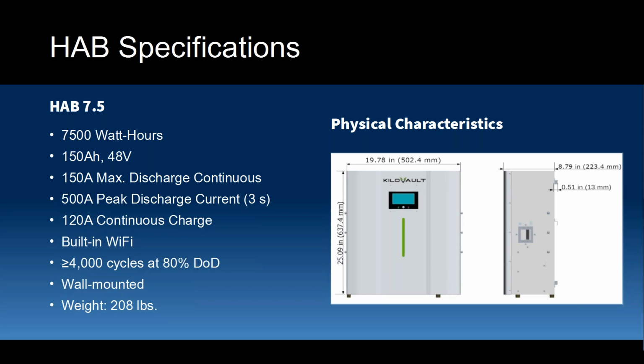At 80% depth of discharge, you'll get approximately or at least 4,000 cycles. We rate it like that because it really depends on how you are cycling the battery. If you're always charging and discharging at the max allowable current, you'll probably get 4,000 cycles on the money. If you're using the battery in a less aggressive setting, you'll certainly get more than 4,000 cycles.